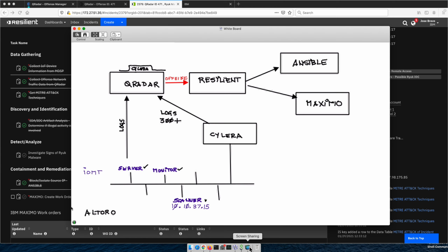There are way too many of them, and so you need a sophisticated asset management tool to work on it. And I just want to point out that also Cylera shared vulnerability data with those two systems. So it is what it found, and that's very unique in the way that it finds the vulnerability of medical devices. These two systems are already aware that that particular MAC address with that scanner has those vulnerabilities.